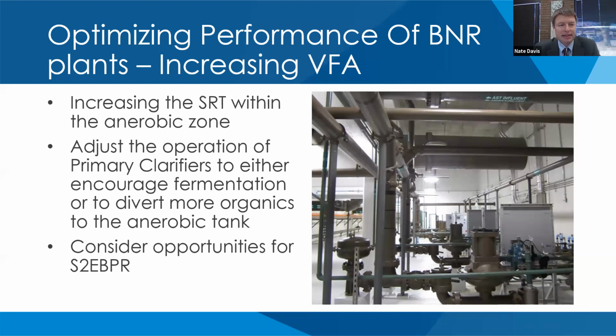They did this slowly over time and monitored it and really found the sweet spot where they could see a decrease in their nitrates in their sludge, but avoid any anaerobic conditions that produce a secondary release of phosphorus, and they prevented any floating sludge. So it's really just that fine tuning there.